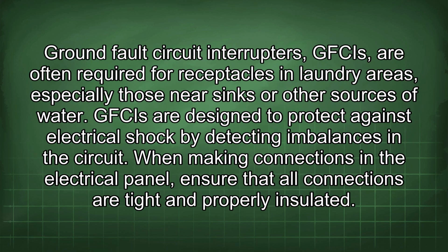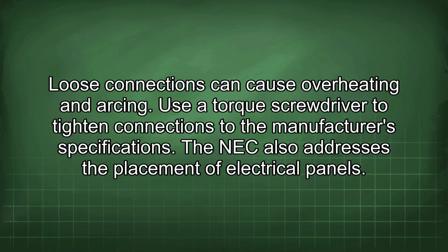Ground fault circuit interrupters (GFCIs) are often required for receptacles in laundry areas, especially those near sinks or other sources of water. GFCIs are designed to protect against electrical shock by detecting imbalances in the circuit. When making connections in the electrical panel, ensure that all connections are tight and properly insulated. Loose connections can cause overheating and arcing. Use a torque screwdriver to tighten connections to the manufacturer's specifications.